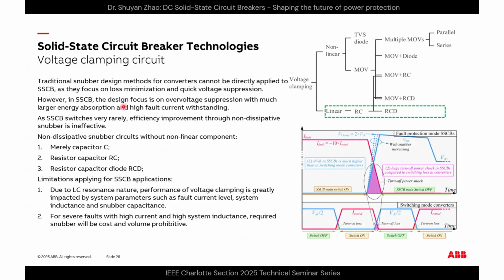Laser here, okay. So traditional snubber design methods for converters produce a waveform like this, but this cannot be directly applied to solid breaker snubber or voltage clamping circuit design, because converter snubbers focus on loss minimization and quick voltage suppression. However, in solid breakers, the waveform looks different. The design focus of this snubber circuit is on overvoltage suppression with much larger energy absorption capability and high fault current withstanding capability. Since solid state breakers switch very rarely, energy improvement through non-dissipative snubbers is not that important or effective.